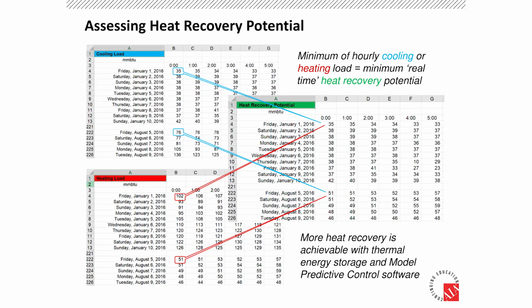But the fact is, buildings have to be cooled, and a lot of modern buildings do simultaneous heating and cooling. You might temper air down to knock humidity out of it, and it gets too cold, so you have to warm it back up before it goes into the building. That's a big opportunity: if you're removing heat from the building through cooling and you need heat for hot water, the heat pump can take care of both.